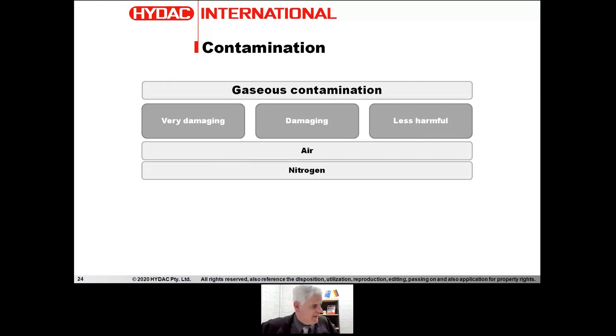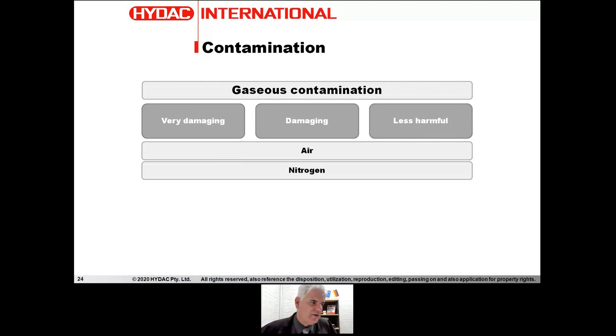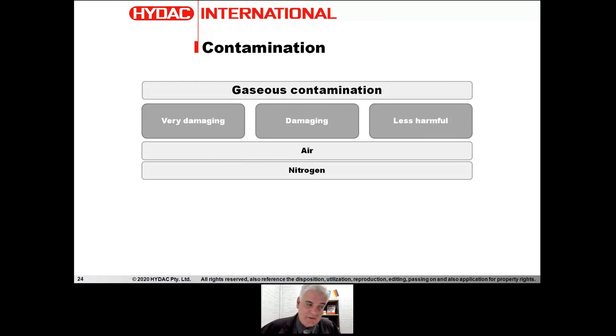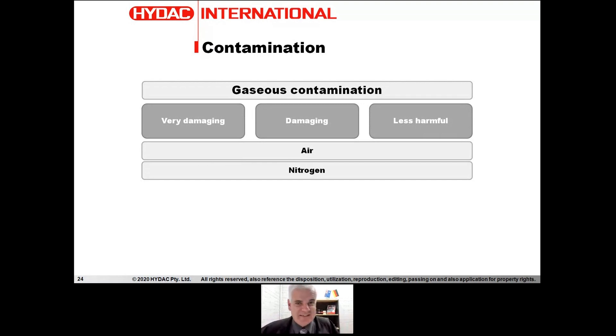Nitrogen can also be a gaseous contaminant. If you have a hydropneumatic accumulator and it loses its bladder, the nitrogen can't go into the atmosphere, so it goes into the oil and bubbles through the system and out of the breather eventually. So if you do have a gaseous contaminant in your system, it could be nitrogen making its way out.